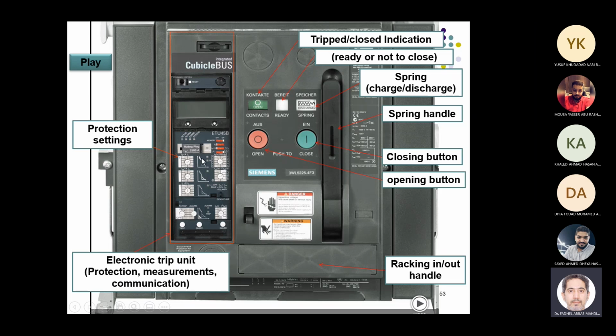So I can set, let's say, the overcurrent elements, or the ground elements, and I can change the time delay and the pickup settings from these. I also have start and stop buttons here, and a lever where I can charge a spring, which you need when you want to close or open a breaker. So you need to charge it. The speed at which the breaker opens relies on a spring. You compress a spring so that when there is a fault or you want to open a breaker, the spring helps the breaker contacts open very fast.